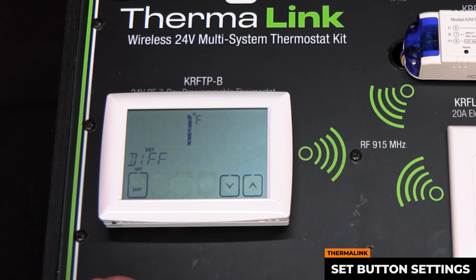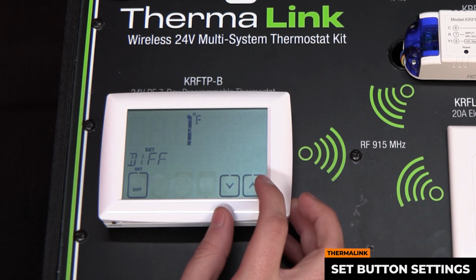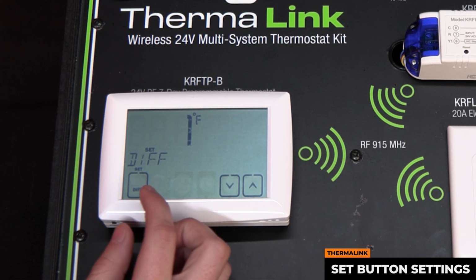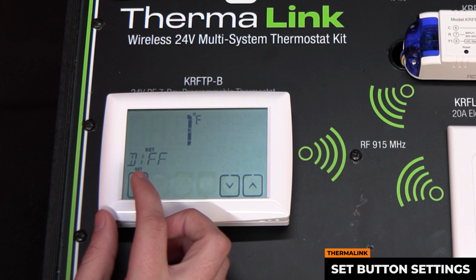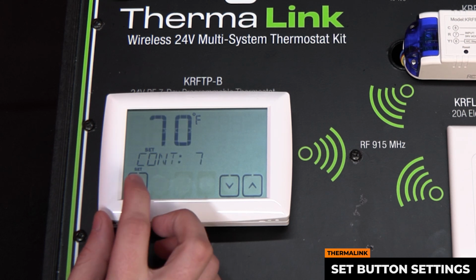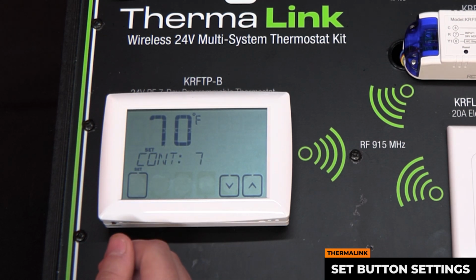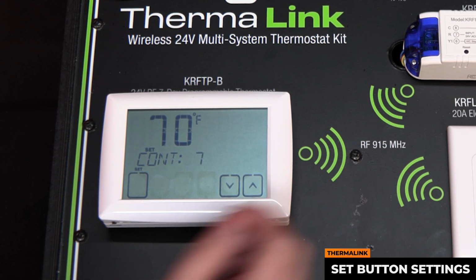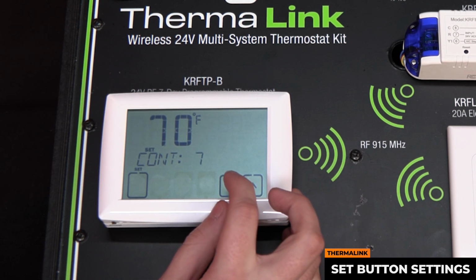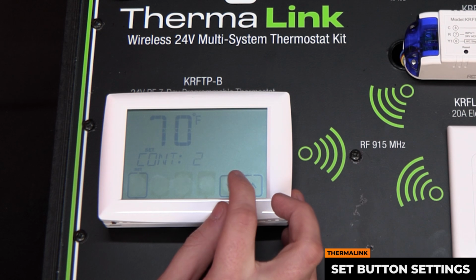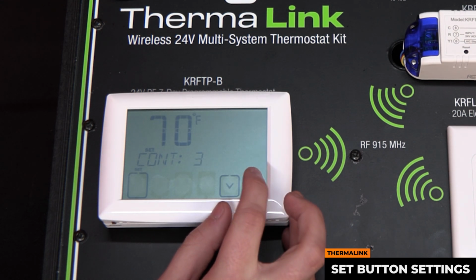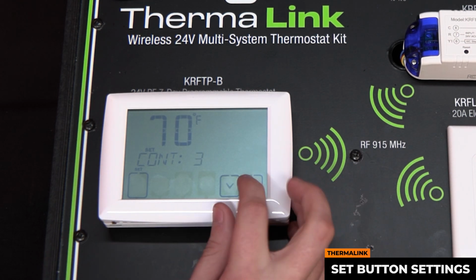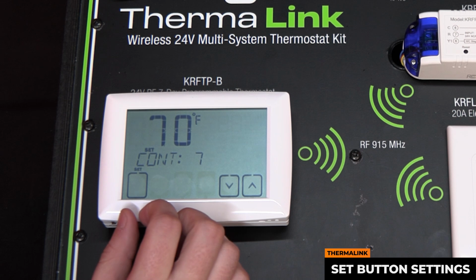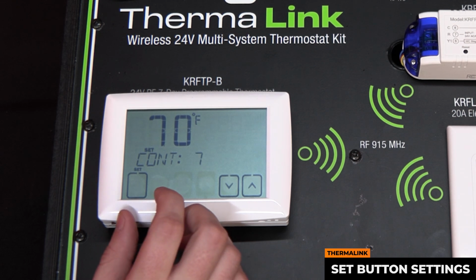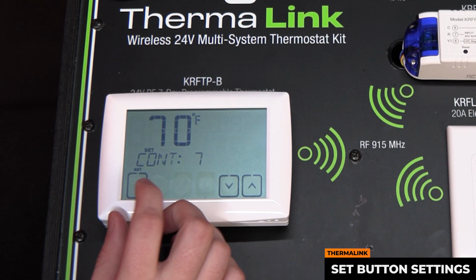Differential, this is your first stage of heat. It's either going to be 1 degree or 2 degrees, but it's default 1 degree. So this is when your heat or cool would turn on 1 degree after the set point. And then your contrast, sorry. This will determine how dark the screen is. If you're in battery mode, it is recommended a 3 or lower. If you're wired, a 7, because you're not worried about battery life.